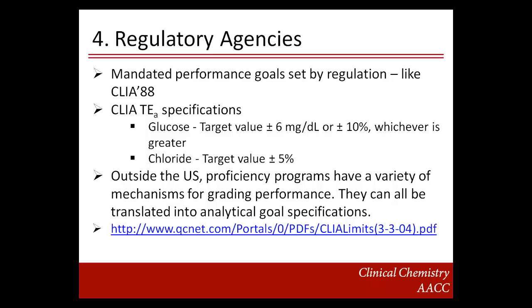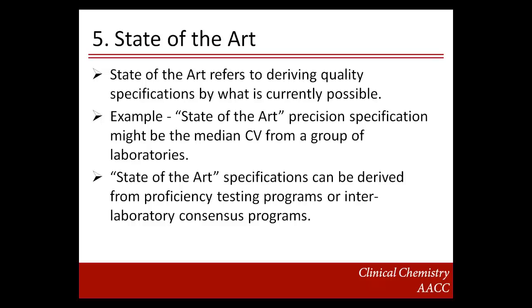Outside the U.S., there are proficiency programs with a variety of mechanisms for grading performance that can all be translated into analytical goal specifications. The last in the hierarchy is quality specifications based on state-of-the-art, which refers to deriving quality specifications by what is currently possible. An example might be taking the median CV from a group of laboratories. State-of-the-art specifications can be derived from proficiency testing programs or interlaboratory consensus programs.